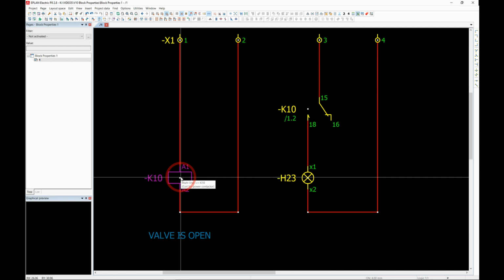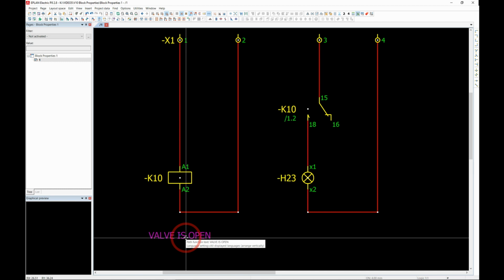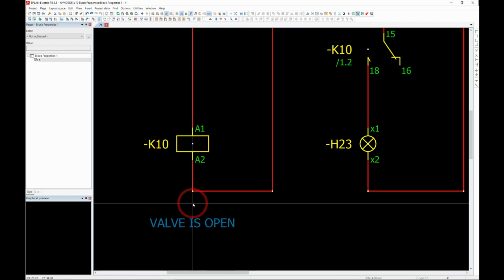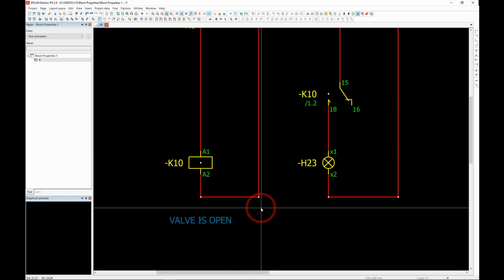That's what I want. For IEC users, it's a top to bottom relationship. Typically the path function text is on the bottom, right here at the bottom of the page, right? Or the object. For NFPA users, it's typically on the right-hand side. Or if you split it up for inputs and outputs, that's left-hand side for inputs or right-hand side for outputs.